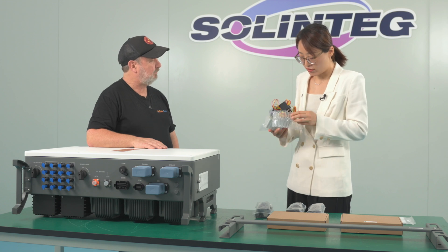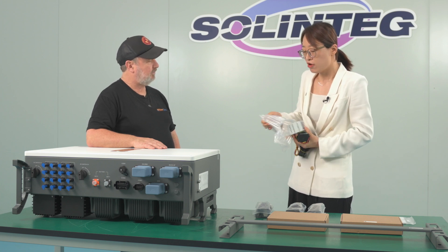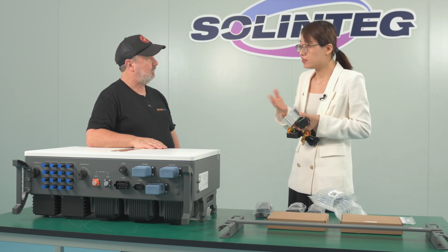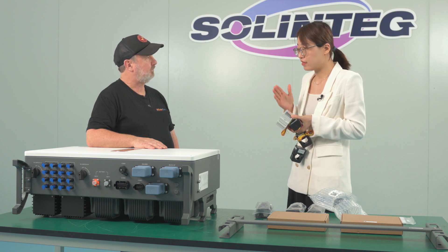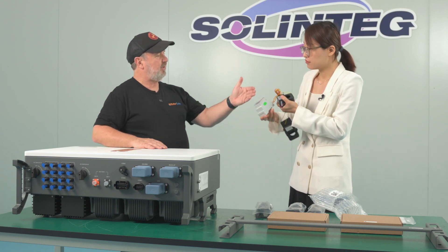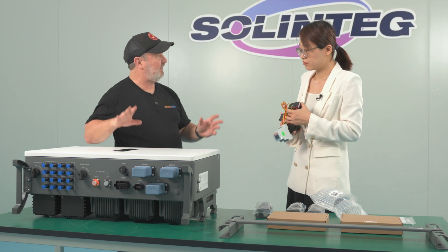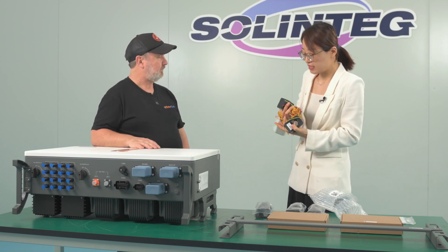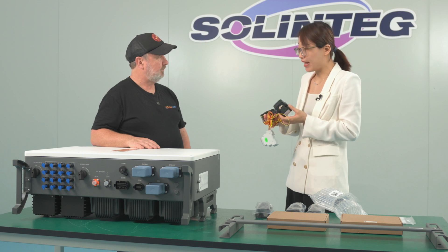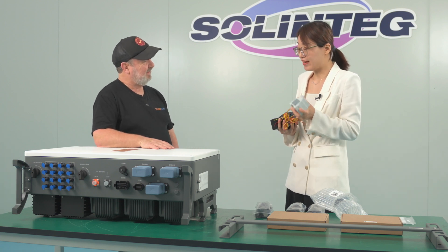This larger box is our smart meter. The smart meter is a device used to detect the upstream current of the system. When the smart meter detects current flowing upstream to the grid, it gives a signal to the inverter to stop or decrease power generation, ensuring there is no excess power exported to the grid. Our smart meter has three integrated CTs, and each CT supports current up to 300 amps, which meets most demand scenarios.